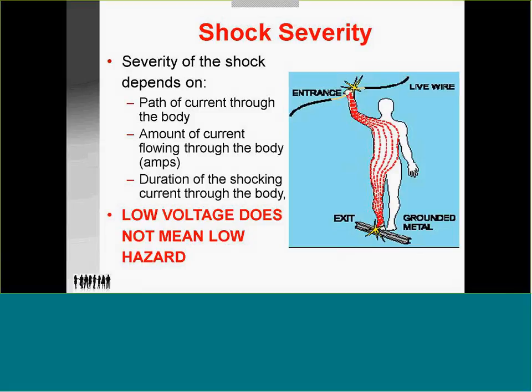Now, you must understand in the code what low voltage means. In NFPA 70, the National Electrical Code, low voltage is anything below 1,000 volts, and 1,001 volts or greater is considered high voltage. The National Electrical Code is now bringing in medium voltage, which is approximately 1,001 to 4,800, and then above 4,800 becomes high voltage. Now, 30 volts can enter the body. It may be a little less than 30 volts.